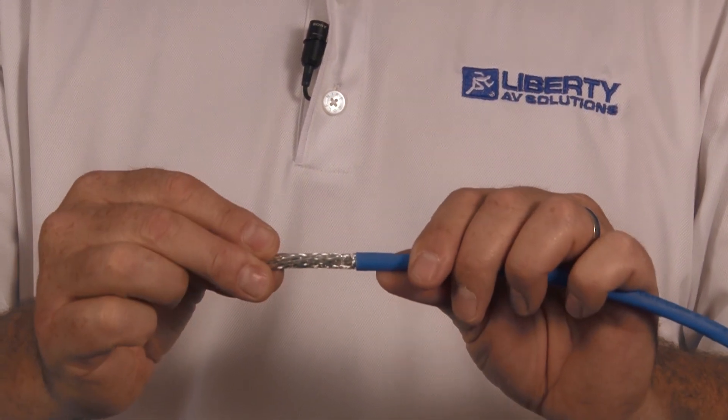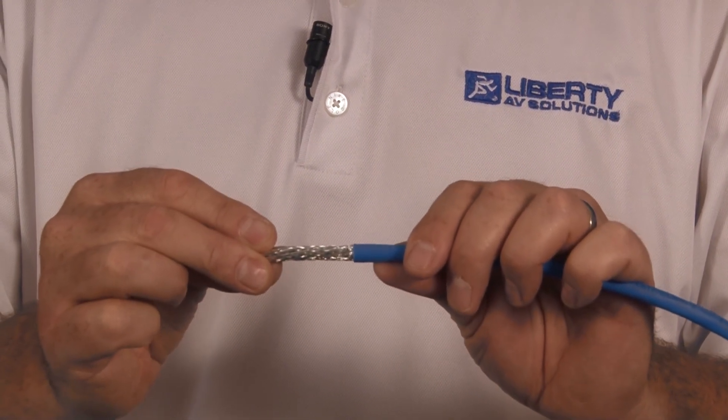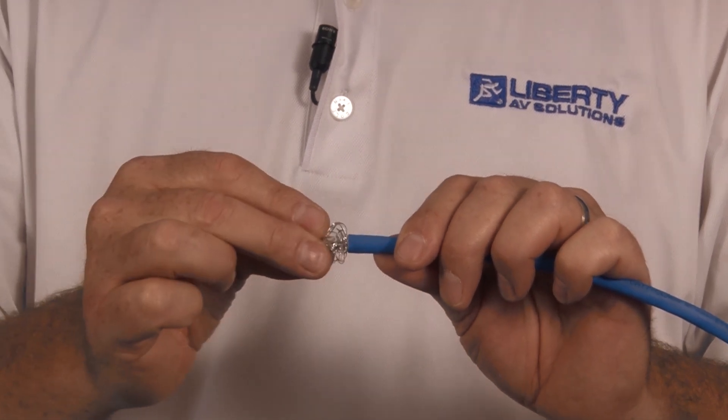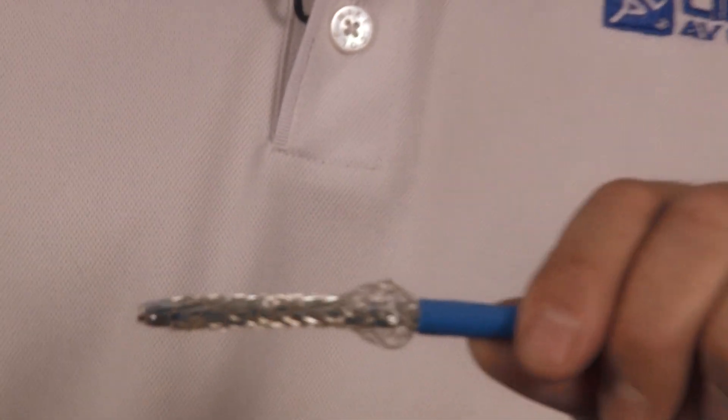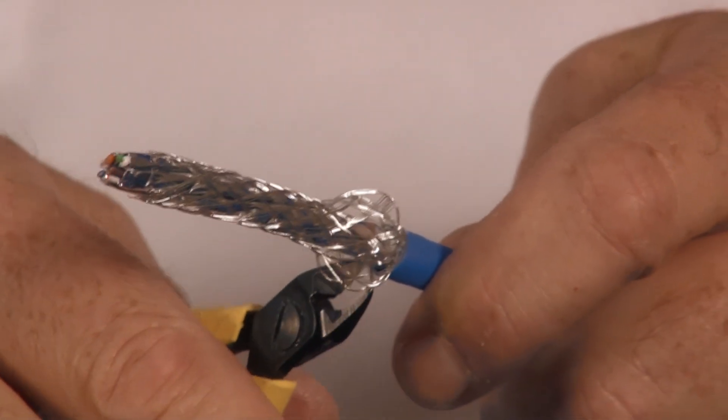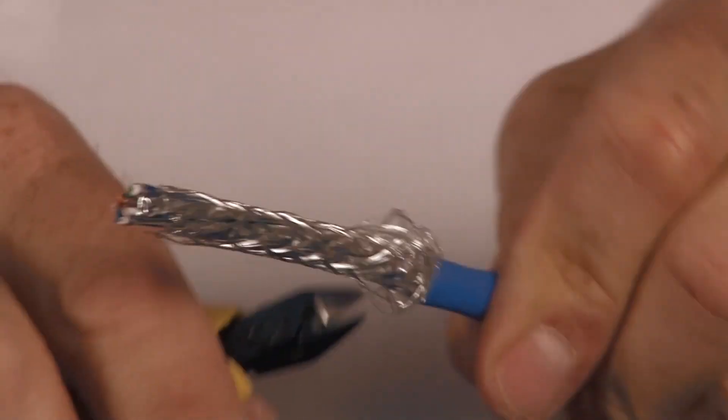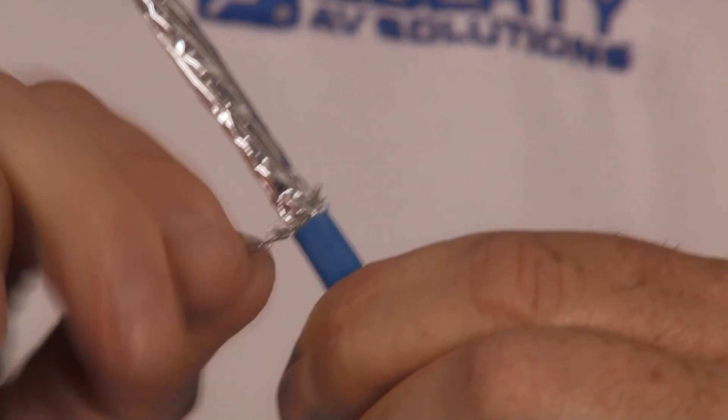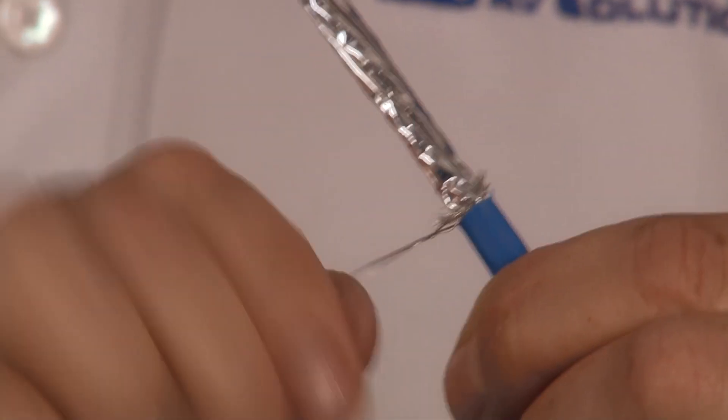First thing I want to do is remove the braid shield and I don't want to remove it all because I want to keep a couple strands to use as a drain contact. So I push on it to birdcage it and then I'll use a pair of diagonal cutters and trim off the braid. I kind of form that into a little pigtail, give it a little twist, fold it back against the jacket.